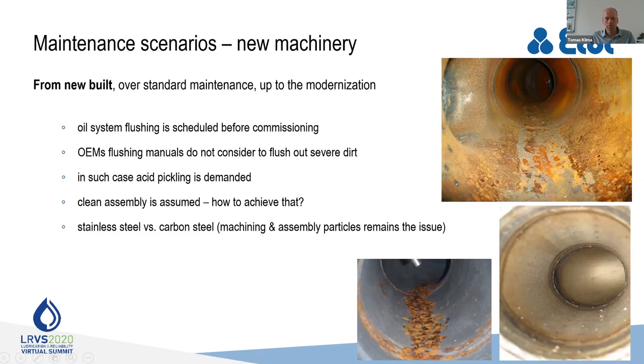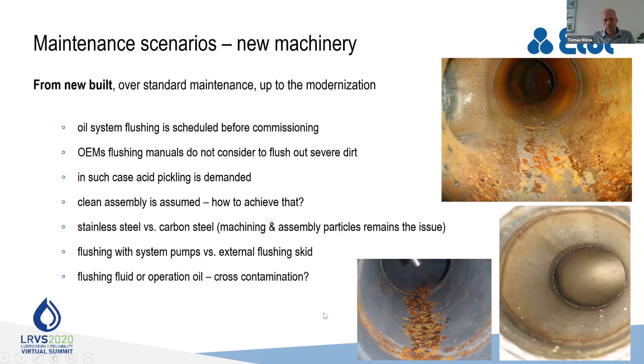Stainless steel is good; it is worth paying some money more to have non-corroded steel. However, the machining and assembly is still the issue. A lot of particles enter the pipes and the system, and you need to get rid of that. Flushing it with system pumps, where the flow is very limited and laminar, is of course not as good as flushing with an external skid. And flushing with operational oil is possible if you take care of the system and you remove all deposited chemicals from the pickling or other anti-corrosive protection and so on.